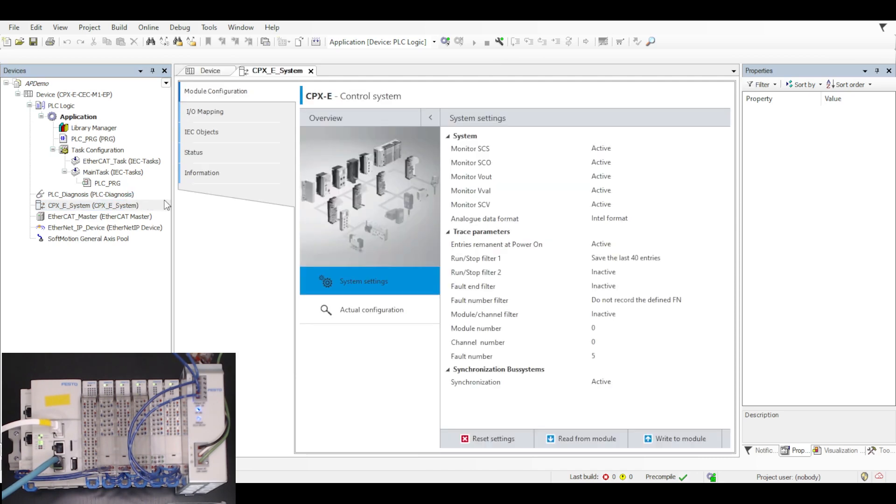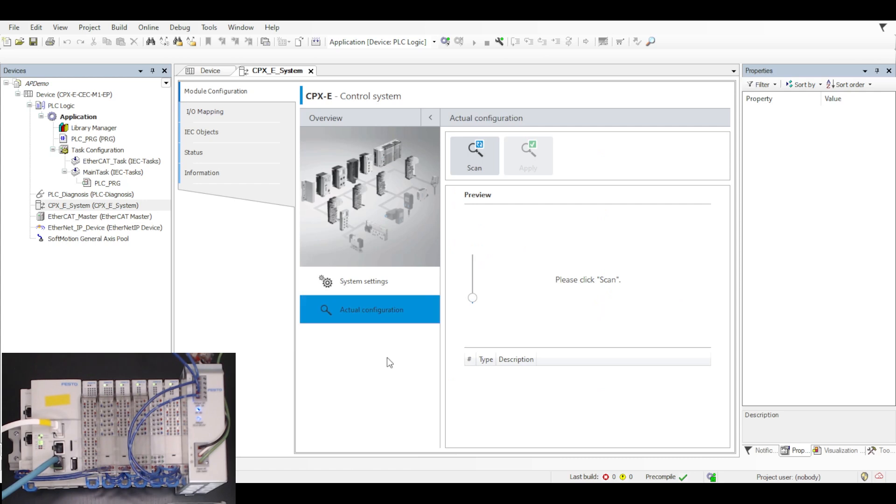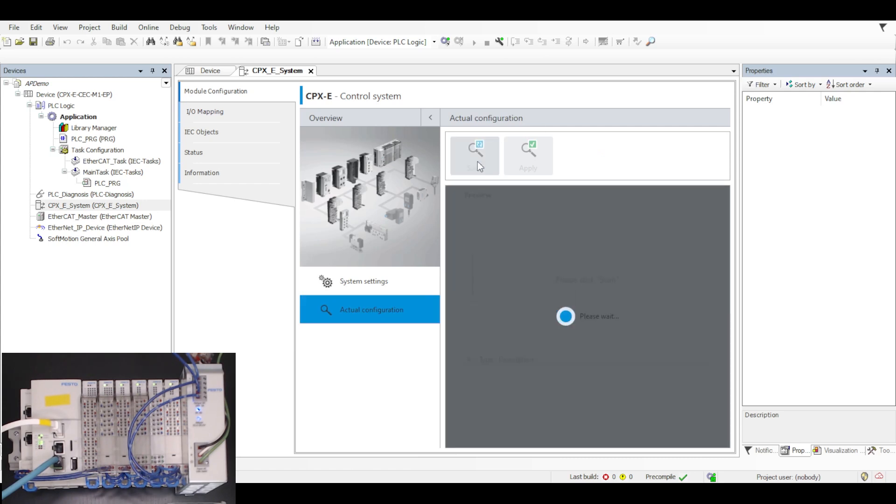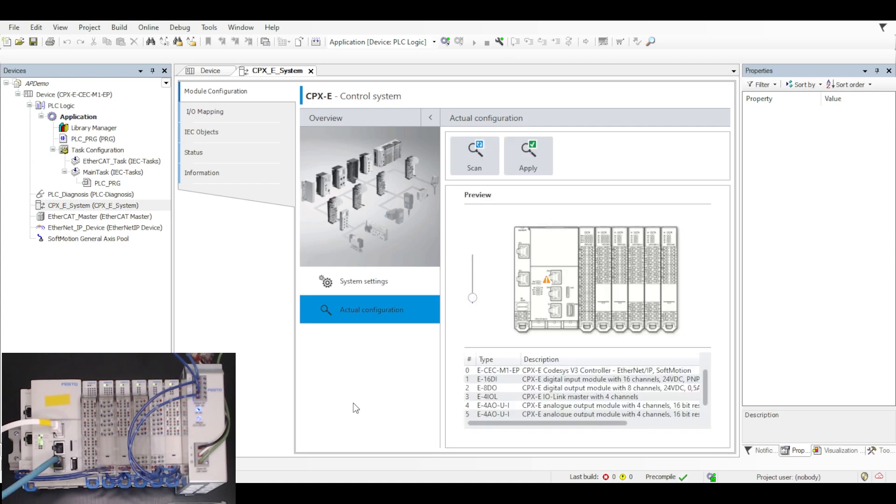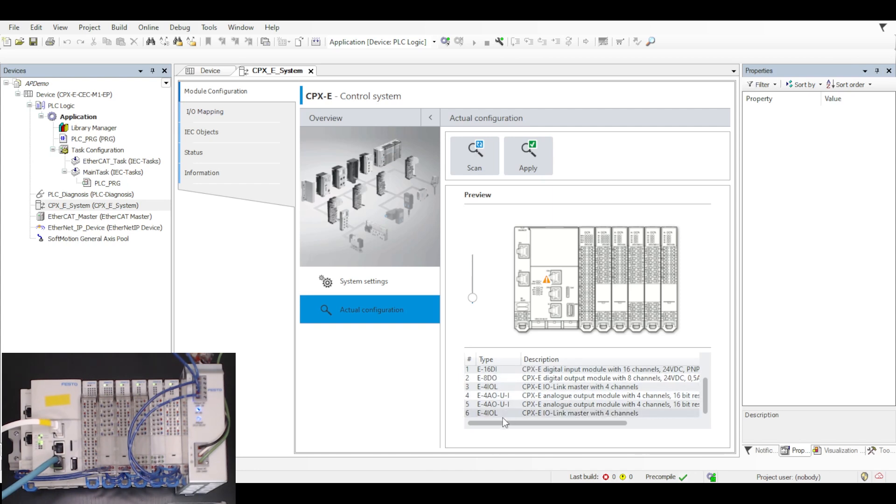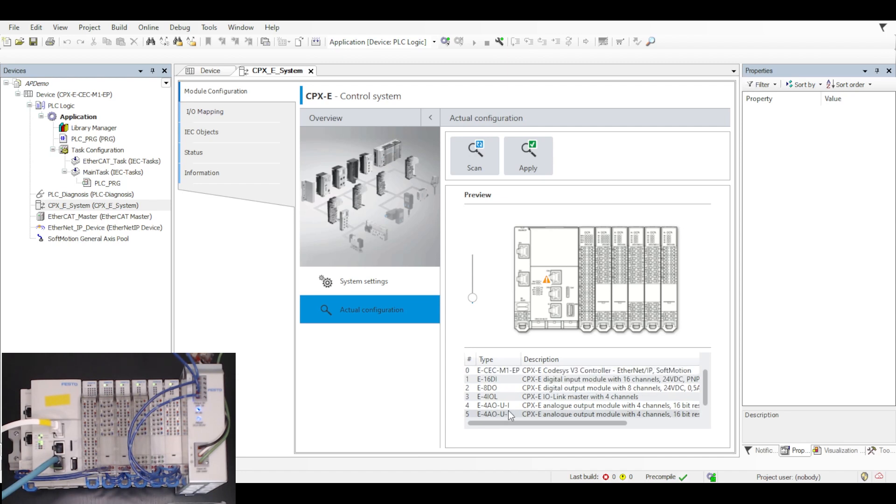Now if I double click the CPXE system on the left hand side under devices and click actual configuration, I can scan for the IP20 slices to the right hand side of the main PLC. So I'll click scan, wait a few seconds, and after that detection is performed, you can see here that I have the PLC at slice 0 and then 1, 2, 3, 4, 5, 6 slices to the right hand side of that PLC.